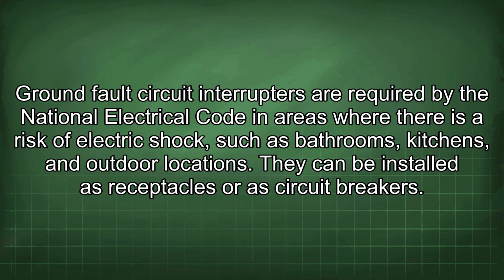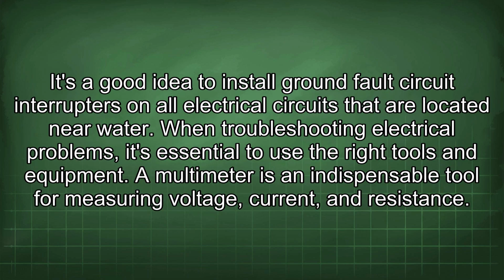Ground fault circuit interrupters are required by the National Electrical Code in areas where there is a risk of electric shock, such as bathrooms, kitchens, and outdoor locations. They can be installed as receptacles or as circuit breakers. It's a good idea to install ground fault circuit interrupters on all electrical circuits that are located near water.